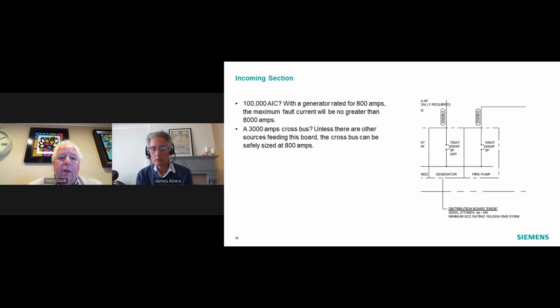Okay, so we're going to look at this section by section. So on the far right, I have that fire pump and I've got the incoming section. But before we get to those, I want to look at what the actual information that's specific to that switchboard shows. And the first thing that we see is that the engineer has called out 100,000 AIC. I was at a seminar several years ago, and Paul O'Hara, who is from Cummins out in California, mentioned to me that the maximum fault current that a generator is going to put out is going to be 10 times what the current rating of that generator is.